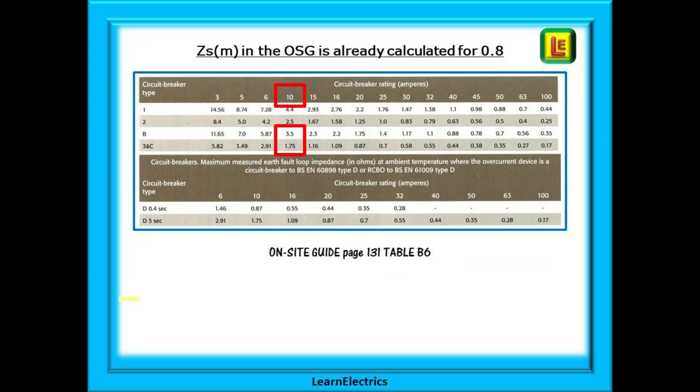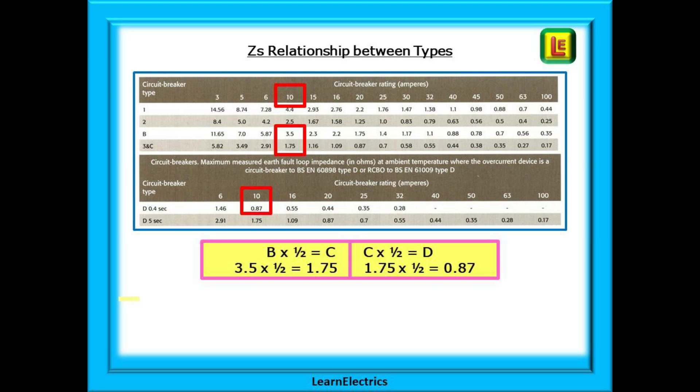Or we can refer to the on-site guide table B6 where all the calculations have already been done for us. The on-site guide shows what we should measure as a maximum with our test meter for each type and rating of MCB. Notice that the C type maximum is half the B type maximum and the D type is half the C type. A useful thing to remember.